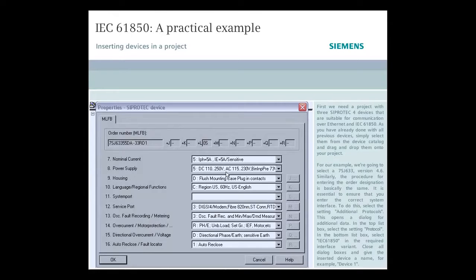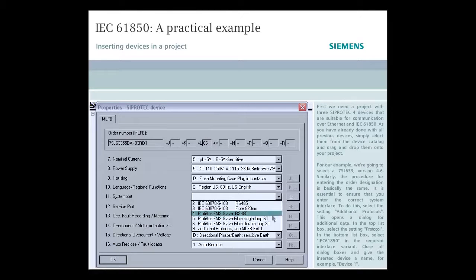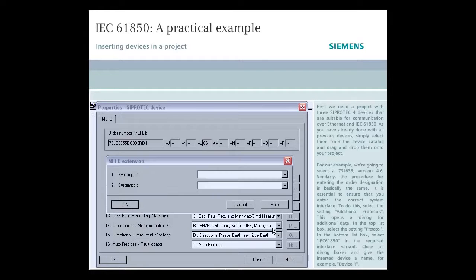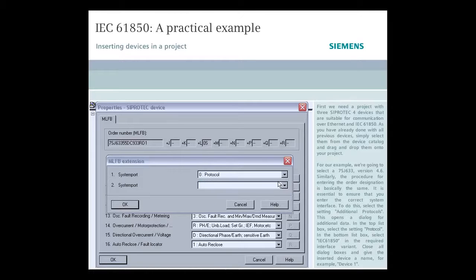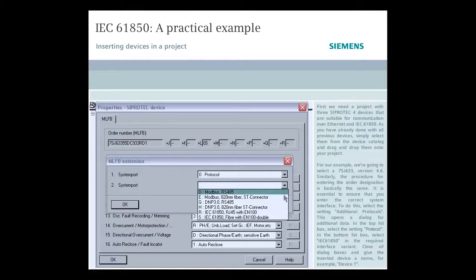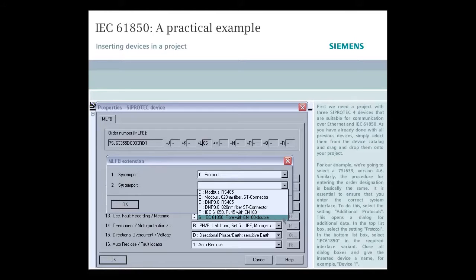It's essential to ensure that you enter the correct system interface. To do this, select the setting Additional Protocols. This opens a dialog for additional data. In the top list box, select the setting Protocol. In the bottom list box, select IEC 61850 in the required interface variant.